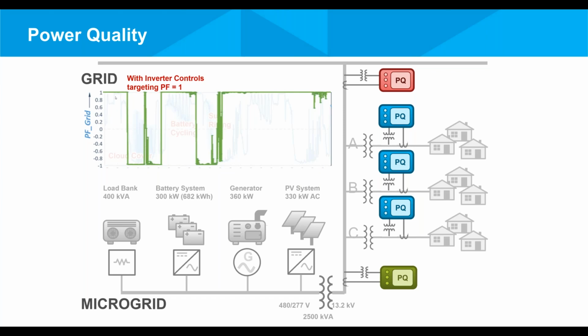You see that the power factor is either at 1 or -1. The 1 or -1 simply symbolizes the direction of power. It basically shows that either power is being generated or power is being absorbed. But the point here is that it's less erratic. The power factor is closer to unity when the inverters are set to control the power factor.